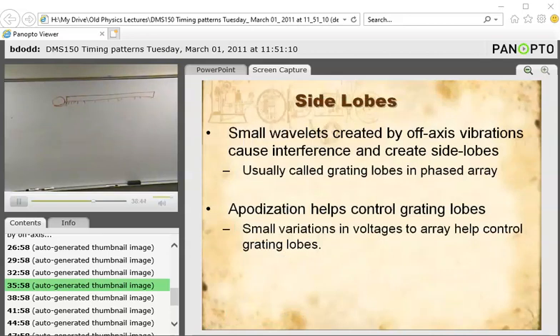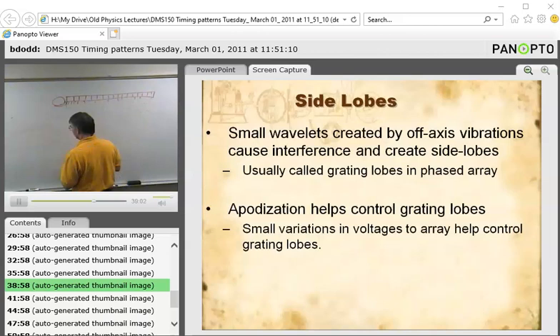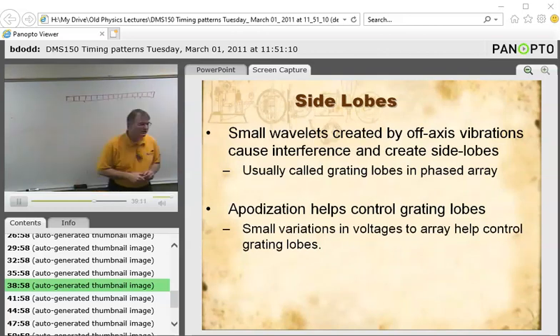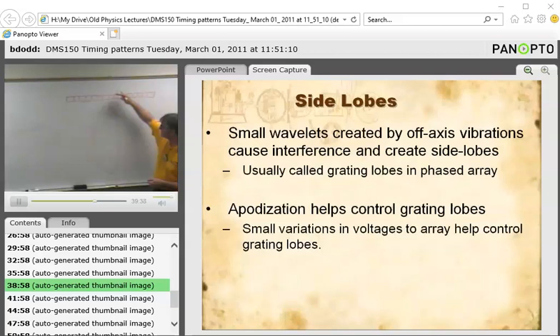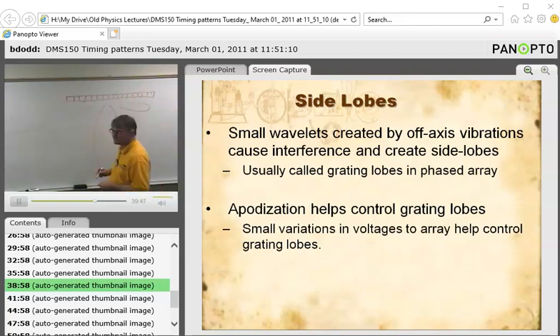All right, so let's talk about side lobe artifacts, and in our transducers that are made up of multiple small crystals, we call them grating lobe artifacts. Now, we talked about side lobe artifacts with the single crystal transducers. Samantha, can you explain to us what the side lobe artifact was? So we create a strong main beam that comes off of our transducer, and then we have these weaker lobes of energy that are coming off to the side, and these are called side lobes.